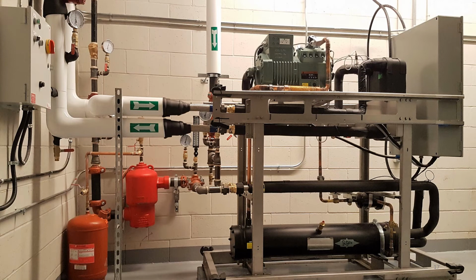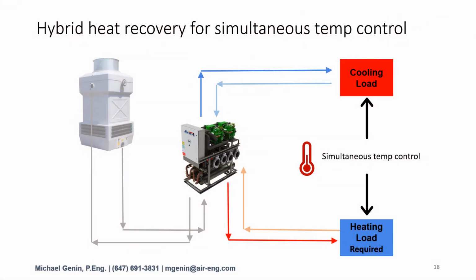These examples are fairly simple, but what happens if your loads are intermittent? Is it still worth implementing heat recovery? This is what I would call a hybrid system. The chiller is designed in such a way that it can provide both the heating and cooling loads. The chiller controls to the cooling load. Heat is recovered for the heating process. If the heating load is satisfied, then we need to reject this waste heat elsewhere. Otherwise, the chiller will be unable to operate. This typically means the implementation of an auxiliary heat rejection method, such as a cooling tower in this case.